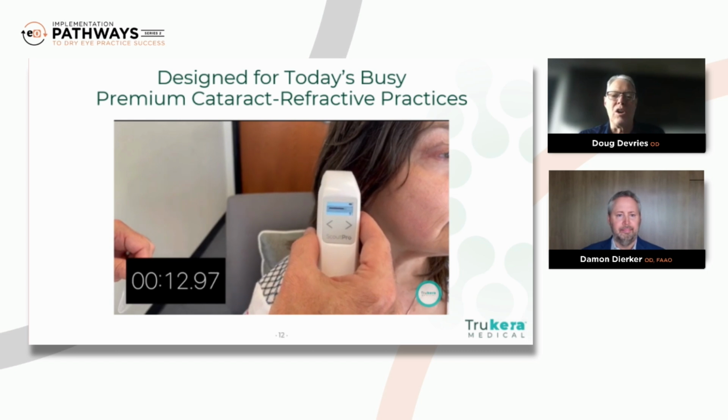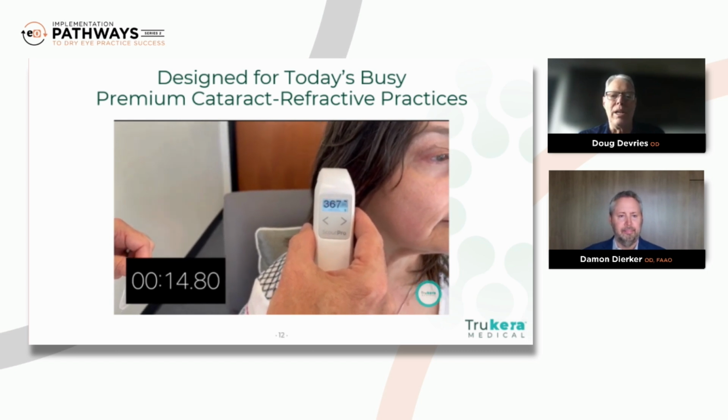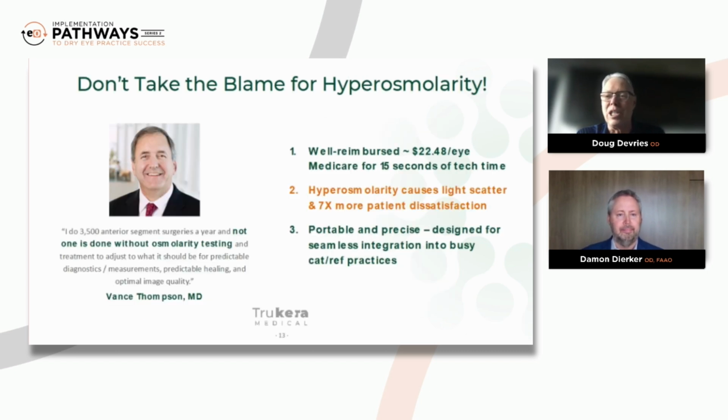So put the test card on, took the test sample, the little microliters of it, and then the results come in less than 15 seconds. So it really is just ease of use. There's no running back to try to dock any of the hand pieces. You're not trying to go through that, get to the exam room, back to the base, setting the test card number, just really fast in terms of patient flow.